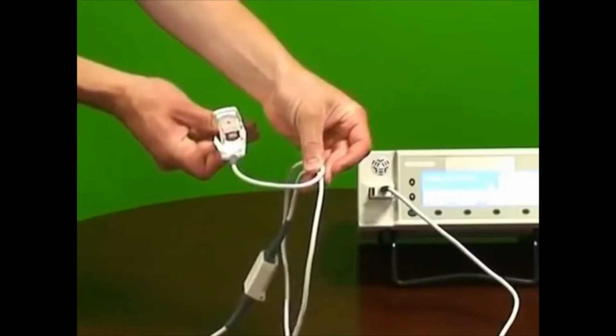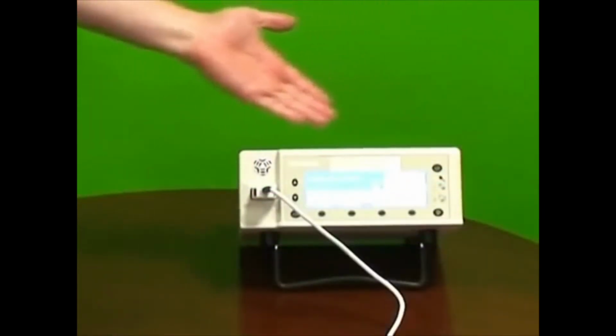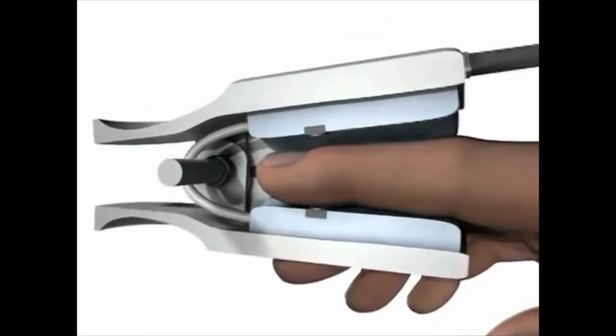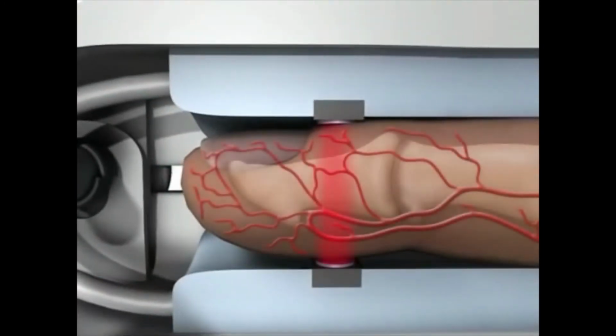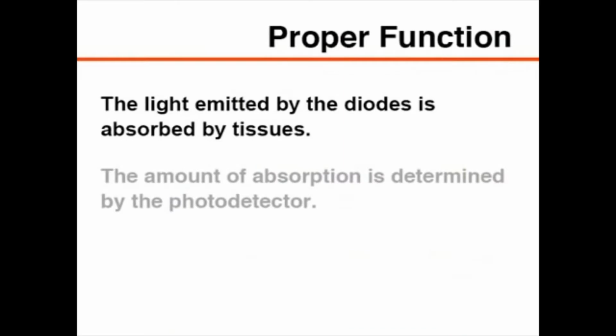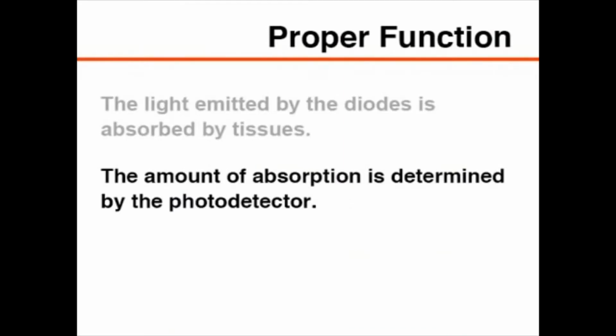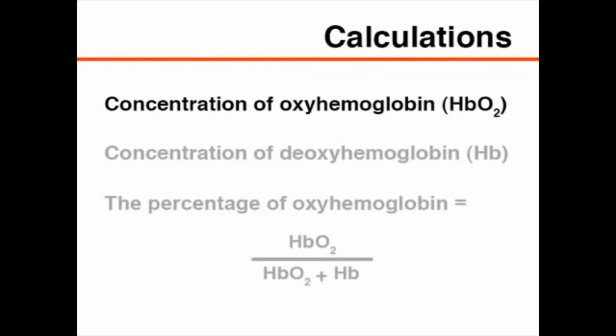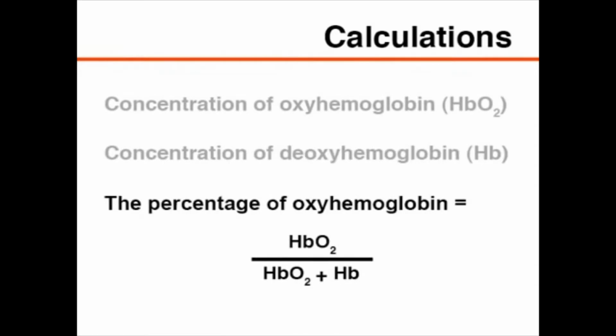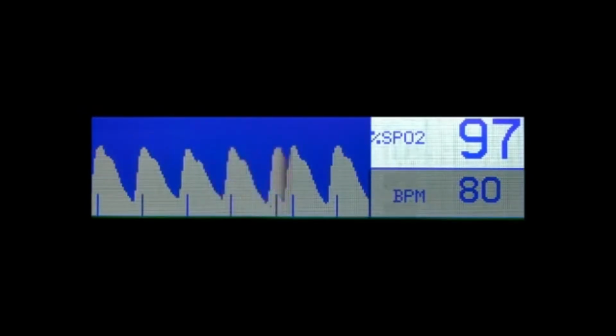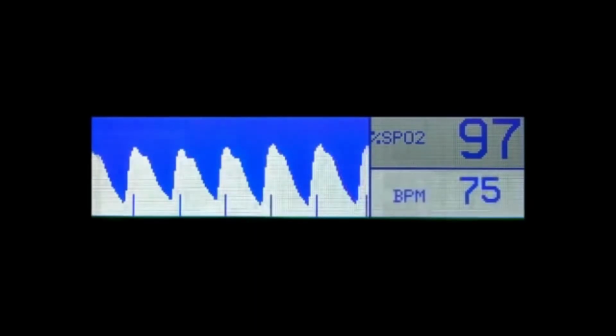Pulse oximeters consist of a peripheral probe and a small microprocessor unit. Traditionally, the peripheral probe contains a photodetector and two light-emitting diodes. The two light-emitting diodes emit light of different wavelengths. The light emitted by the diodes is absorbed by tissues, and the amount of absorption is determined by the photodetector. Using this information, the microprocessor determines the concentration of oxyhemoglobin and deoxyhemoglobin, respectively. It then calculates the percentage of oxyhemoglobin and displays the hemoglobin oxygen saturation in arterial blood, a waveform corresponding to the pulsatile flow in arterial vessels, and the heart rate.